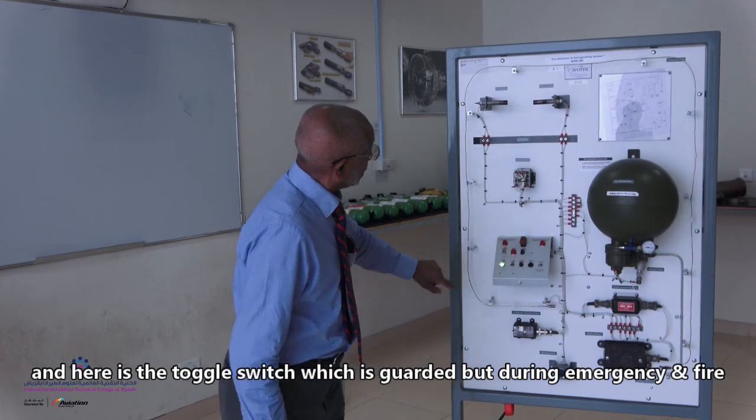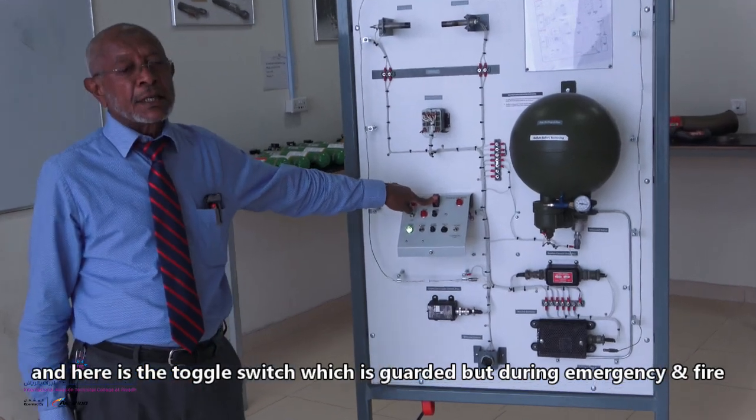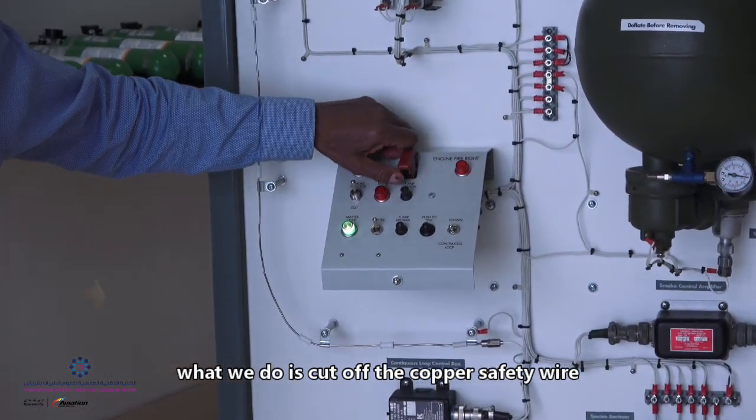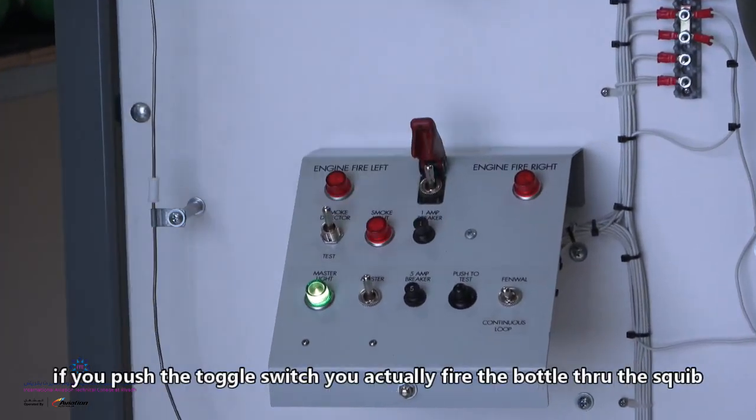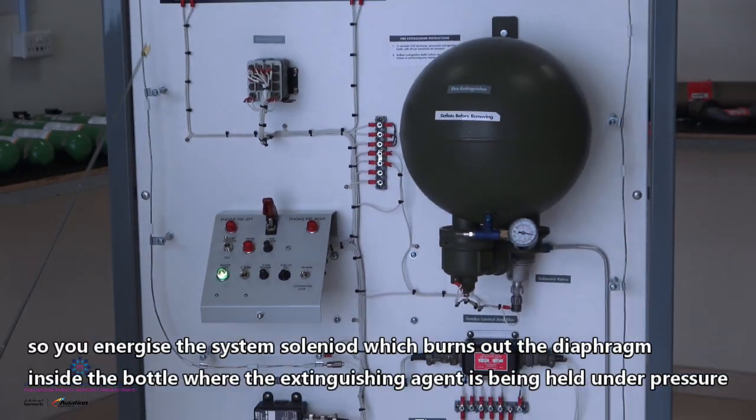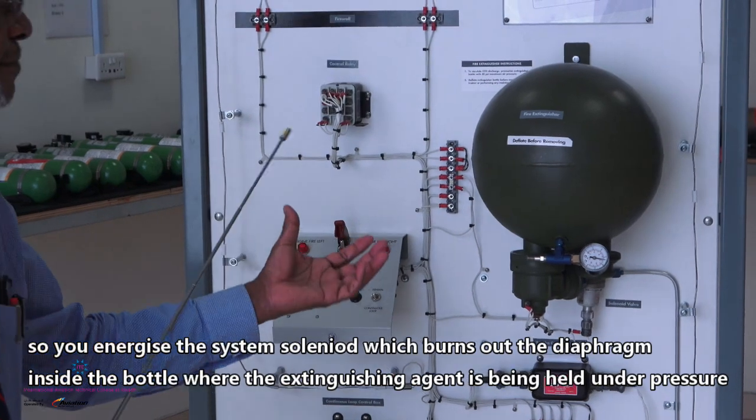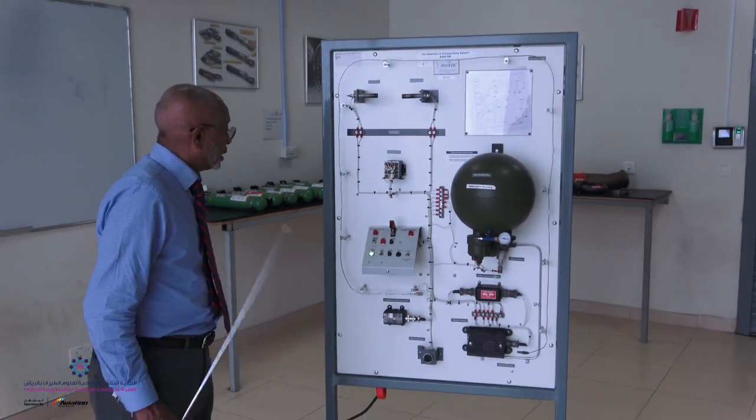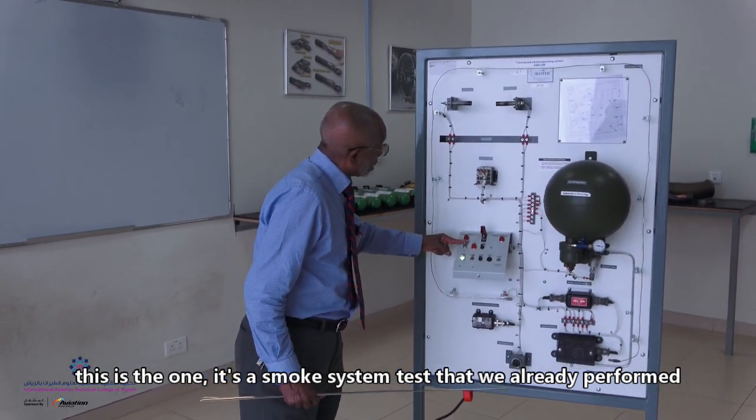As you see here you have the toggle switch. It is guarded all the time, but during emergency and during fire, what we do is we cut off the copper safety wire and then we open it. If you push the toggle switch, you're firing the bottle through the squib, so you're energizing the solenoid which burns out the diaphragm inside the bottle where it's holding the pressure and the agent.